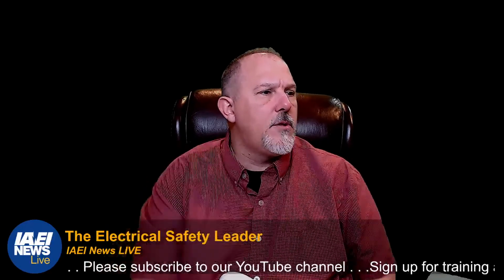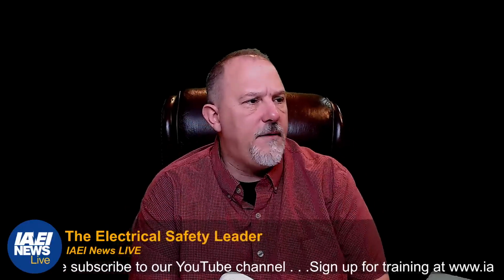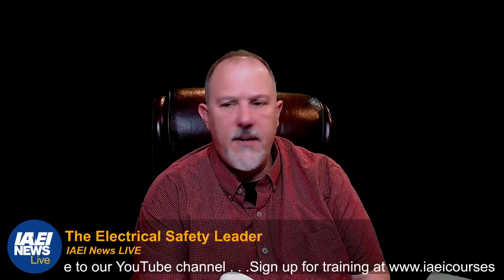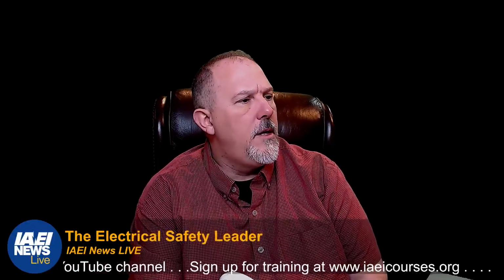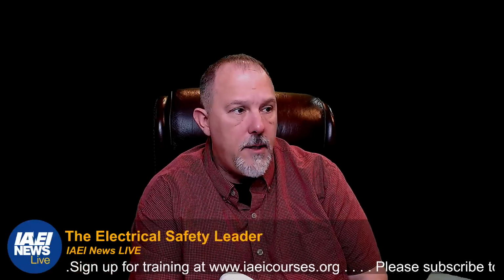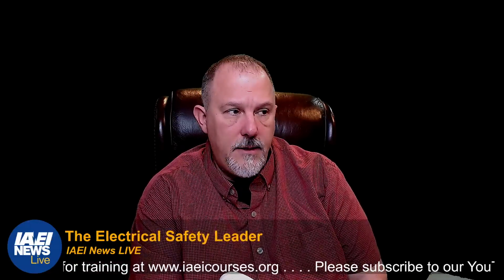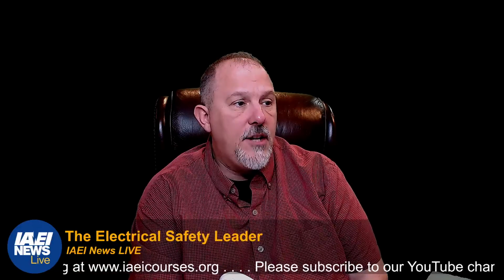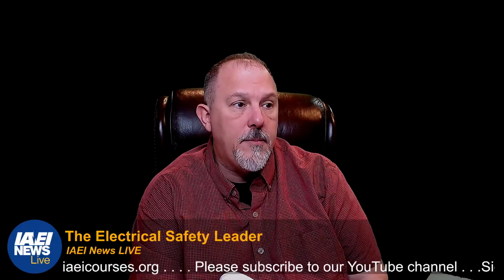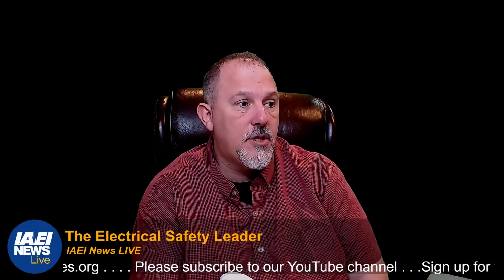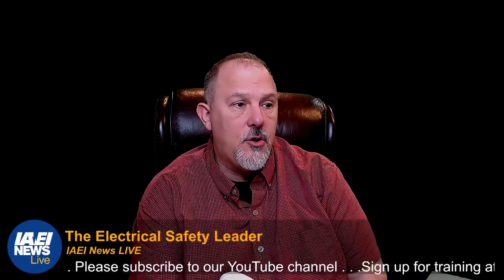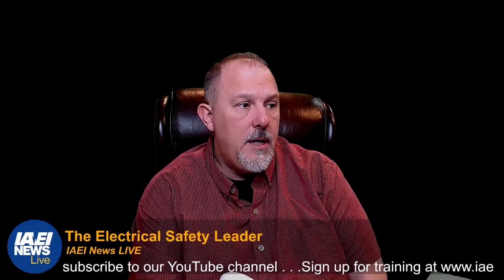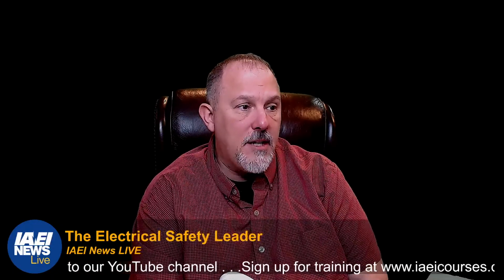EMP principles: it says the EMP shall be designed to function in conjunction with the applicable safety program. The EMP shall include the following elements: an electrical safety program that addresses the condition of maintenance, identification of personnel responsible for implementing each element of the program, survey and analysis of electrical equipment, developed and documented maintenance procedures.